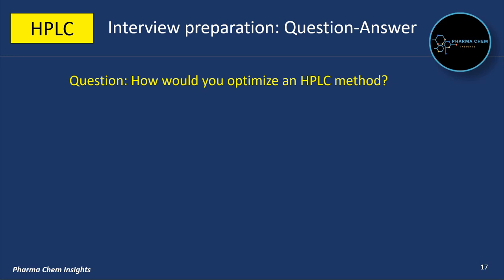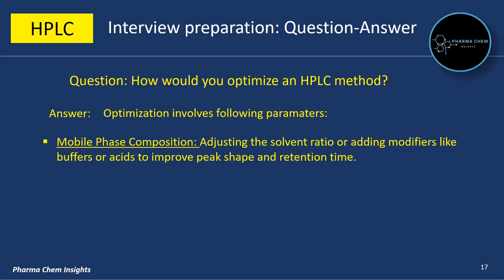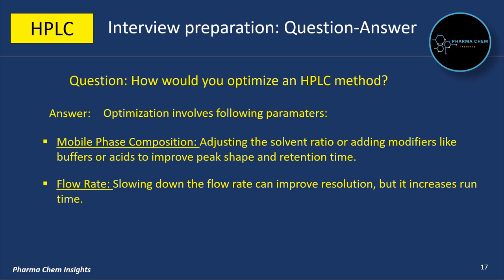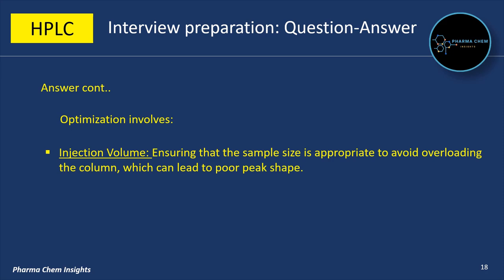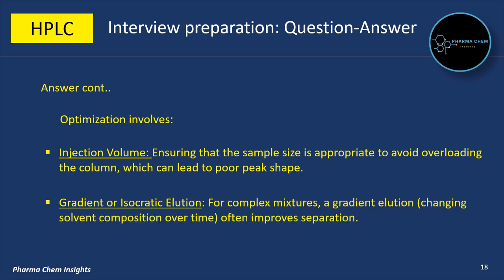Next question: how will you optimize an HPLC method? Optimization involves the following parameters: mobile phase composition — adjusting the solvent ratio or adding modifiers like buffers or acids to improve peak shape and retention time; flow rate — slowing down the flow rate can improve resolution but increases run time; column temperature — increasing temperature can reduce retention times and improve peak shape but may also affect resolution; injection volume — ensuring the sample size is appropriate to avoid overloading the column, which can lead to poor peak shape; and gradient or isocratic elution — for complex mixtures, gradient elution (changing solvent composition over time) often improves separation.